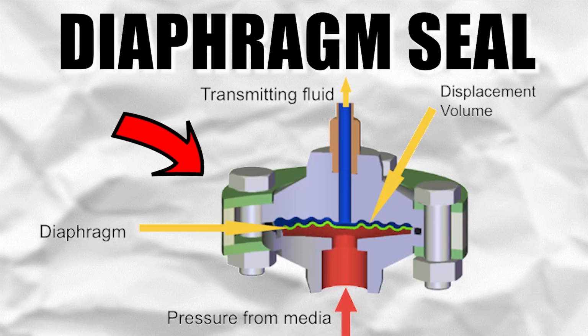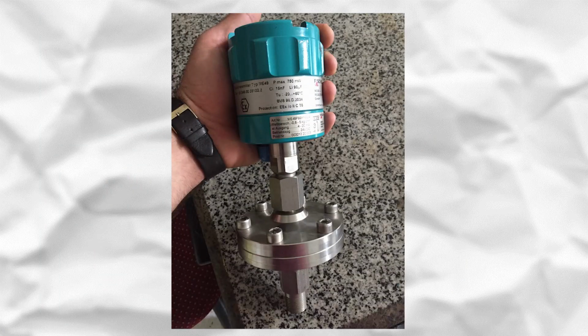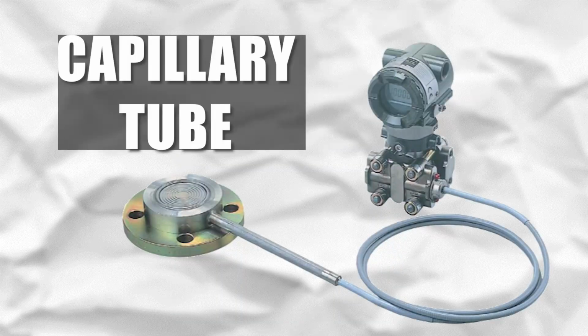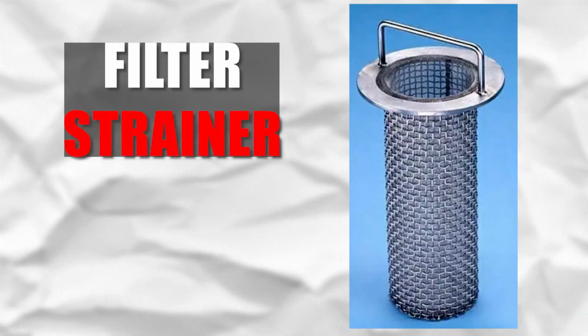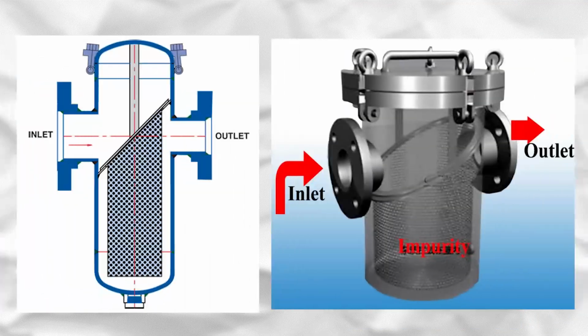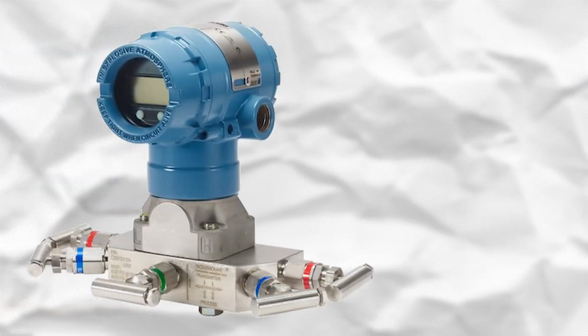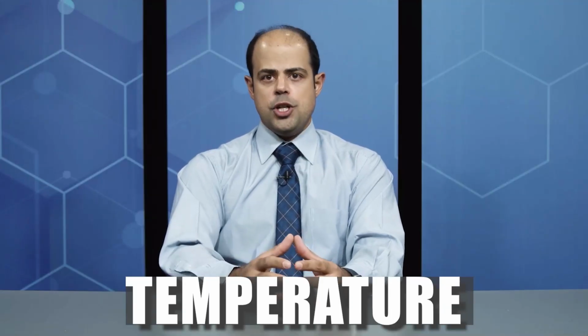There are two important accessories for these transmitters, which are the two-way valve manifold and the diaphragm seal. Diaphragm seals are usually used to create isolation between the measuring instruments and the fluid, which is corrosive or highly viscous. The transmitters are installed on diaphragm seals directly, or you may apply a capillary tube for their mounting. In some special cases, you might use a differential pressure gauge or transmitter. A practical example is a filter or strainer. An operator working in an industrial plant must know the difference between the inlet and outlet of a filter to clean it periodically. You should be notified that the instruments in this category are installed with the help of a 5-way valve manifold.